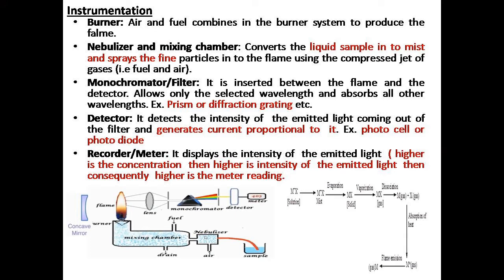When excitation takes place in the flame and the atoms return to the ground state, characteristic radiation is emitted. A concave mirror is kept on the opposite side of the recording device to reflect emitted radiation that would otherwise scatter away. This concave mirror reflects the emitted radiation from M* back toward the lens, and it then reaches the monochromator.